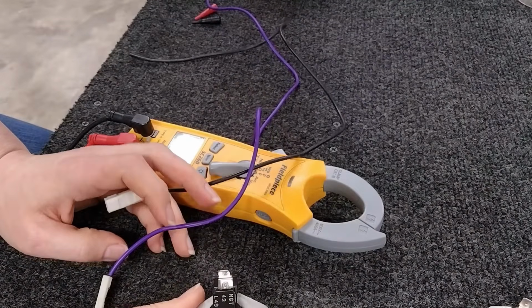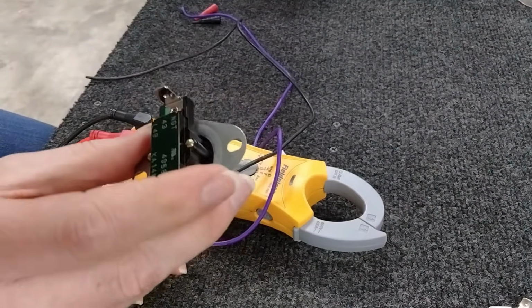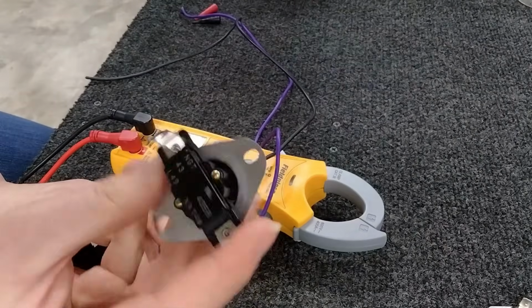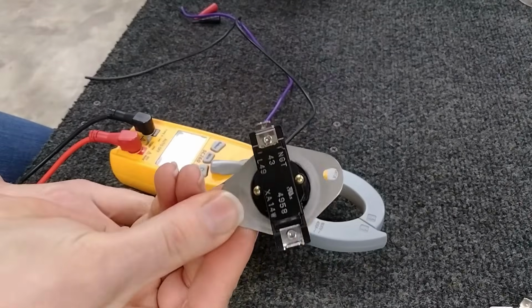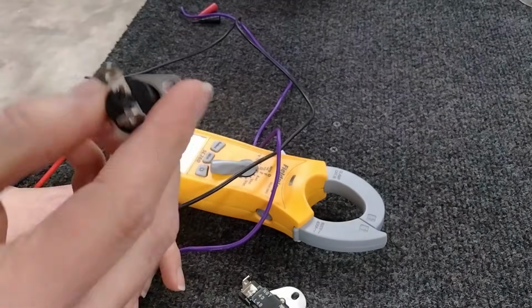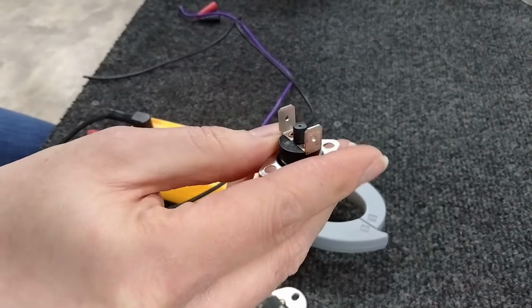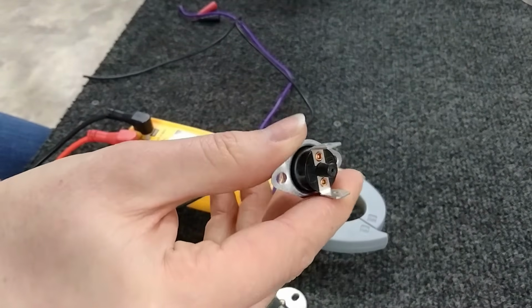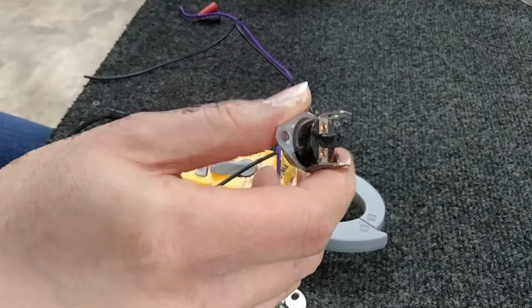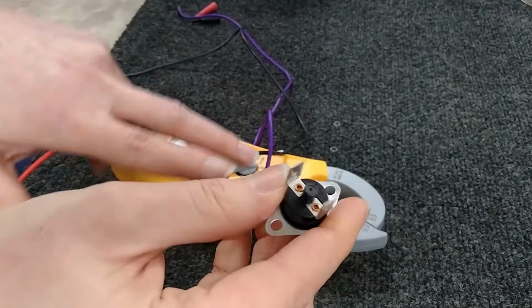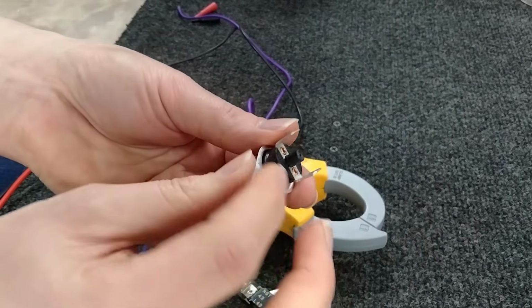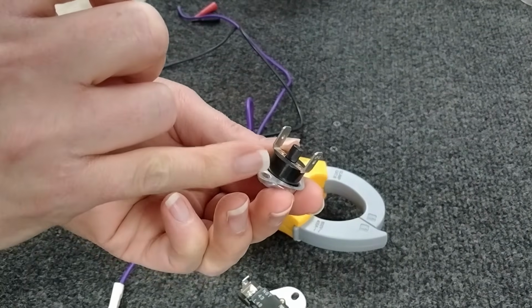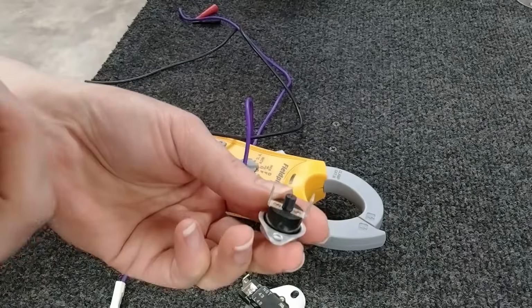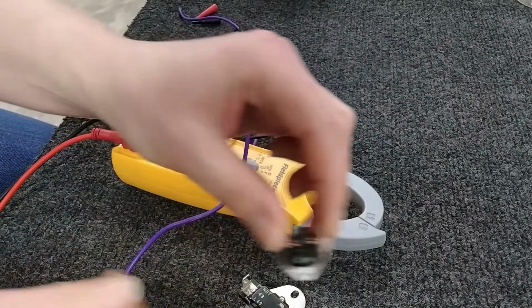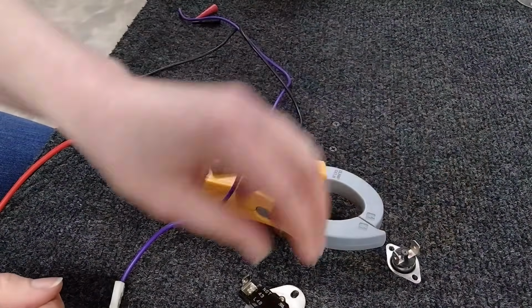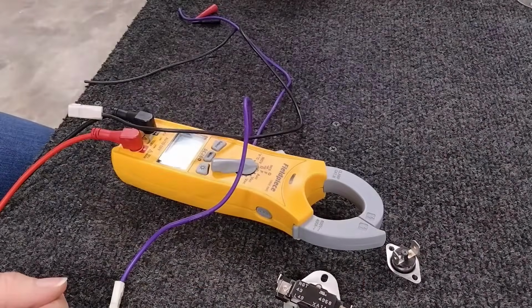Check your automatic ones first, which can be on your blower housing. Some of the older models have them on a plate that's kind of above the burners. There are these kinds that are either on your blower housing or somewhere inside. But instead of having that reset button, it's what we call an automatic limit. It's not going to have that reset button because it's a secondary safety switch instead of your primary. But you do have one more limit that we call a high limit switch.